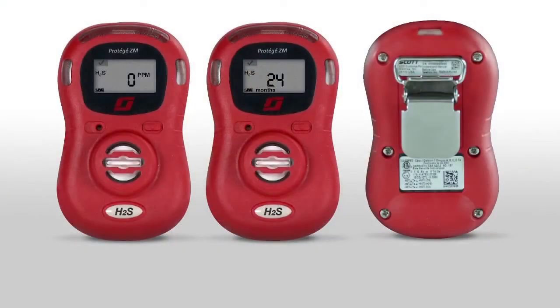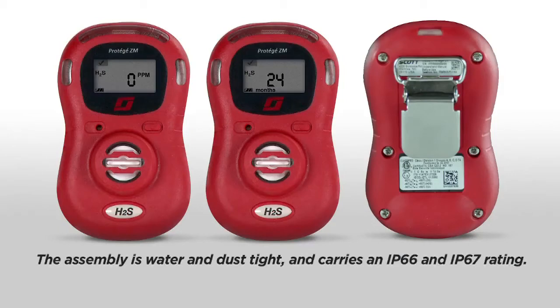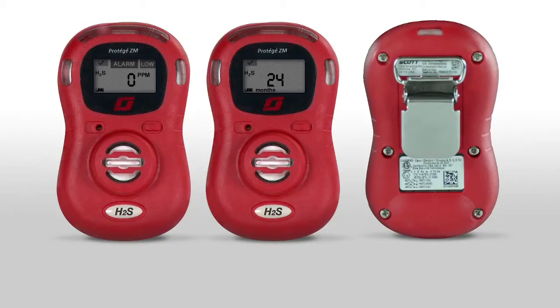Major features consist of the red, high-visibility housing. This housing allows the Protege ZM to be seen from a long distance, and it's easy to find if dropped. The assembly is water and dust tight and carries an IP66 and IP67 rating. The LCD screen will display real-time information and alarms. The LED bars on the top and sides will light up when the product is in alarm, providing wide-angle viewing of the alarms. This is the activation button.